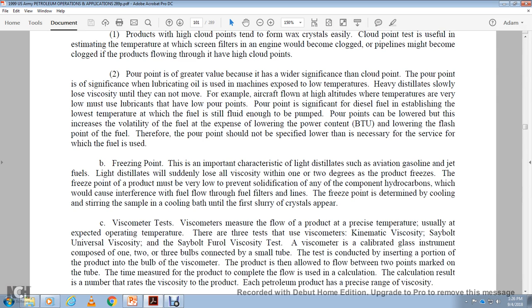Alright, viscosimeter test. A viscosimeter measures the flow of the product at a precise temperature, usually the operating temperature. There are three types of viscosimeter: kinematic viscosity, Saybolt universal viscosity, and Saybolt Furol viscosity. The viscosimeter is a calibrated glass instrument with one, two, or three bulbs connected with a small tube. The product is inserted through a port into the bulb of the viscosimeter and allowed to flow between two marks on the tube. The time for the product to flow is measured and used in the calculation. The calculation result gives the viscosity rate of the product.